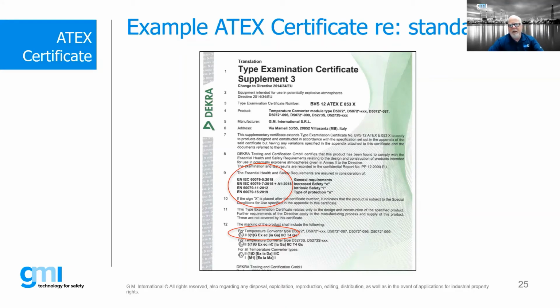So under IEC EX certificates, they do issues. The old one gets replaced - it doesn't mean the old one's no good, it just means the old one is old, and the latest is the greatest. The ATEX directive, or certificates issued by the notified body to the directive, will basically reference the most recent, or they'll stay in chronological order, sequentially, if that makes sense.